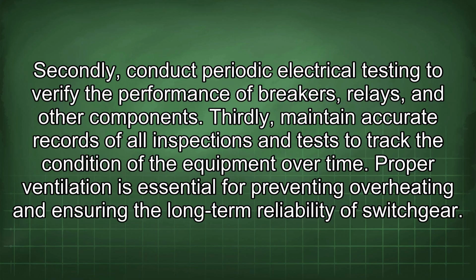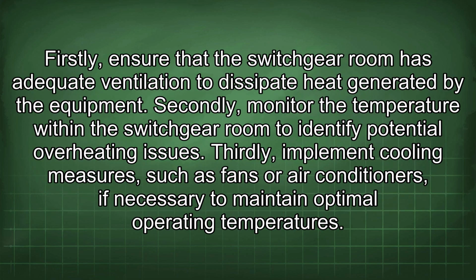Proper ventilation is essential for preventing overheating and ensuring the long-term reliability of switchgear. Firstly, ensure that the switchgear room has adequate ventilation to dissipate heat generated by the equipment. Secondly, monitor the temperature within the switchgear room to identify potential overheating issues. Thirdly, implement cooling measures such as fans or air conditioners if necessary to maintain optimal operating temperatures.